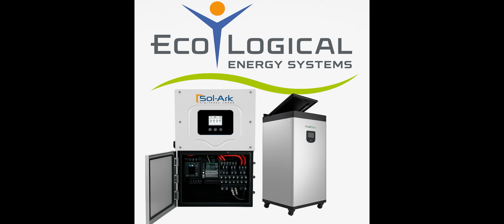Always. And just a quick rundown of the SolArk 15K LV's core technical specs. What kind of power are we talking about here? Key specs for the SolArk 15K LV include a maximum amount of solar panel power you can connect up to 19,500 watts. Big PV array. It works with batteries in the voltage range of 43 to 63 volts. It can handle a very high charge and discharge current of up to 275 amps. Wow. It can continuously output 15,000 watts of AC power, which is substantial for running a whole house. And the inverter itself comes with a standard 10-year warranty. 10 years on the inverter, too.